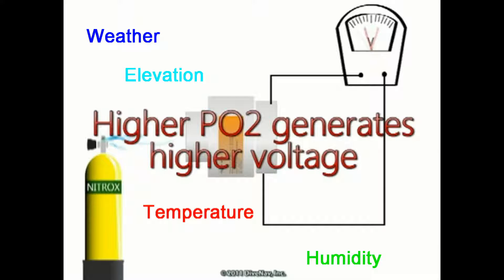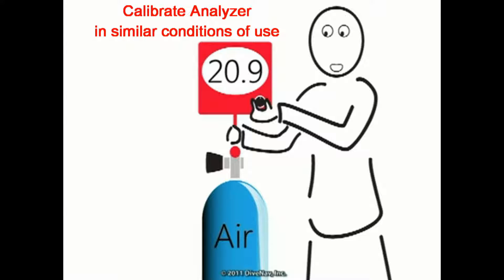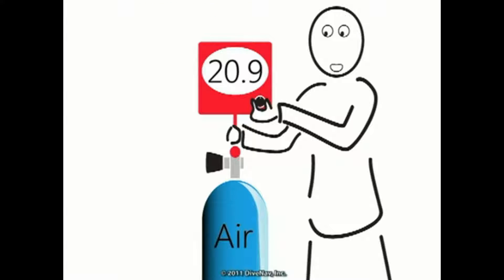Additionally, the oxygen sensor is also affected by changes in temperature and humidity. Therefore, before you use an oxygen analyzer, it must be calibrated with a known reference gas used in similar conditions as the gas you want to analyze. There are three methods to performing an oxygen sensor calibration.